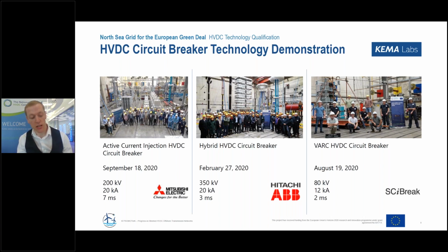The most onerous test undertaken as part of the project had a transient overvoltage of 490 kV with a 20 kiloamp current that needed to be broken, and all that led to 10 megajoules of energy getting put into the test device. So all the testing was undertaken at KEMA Labs, and pictured you can see all the devices tested.